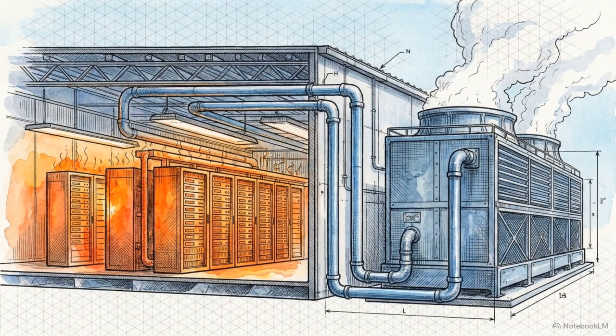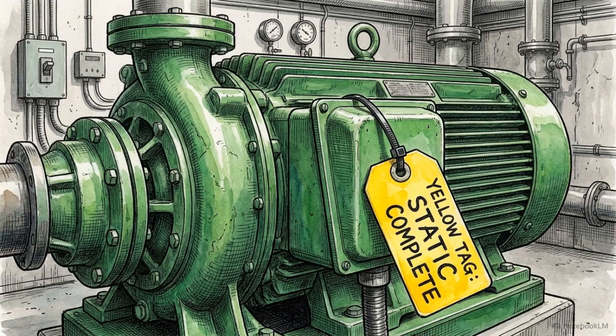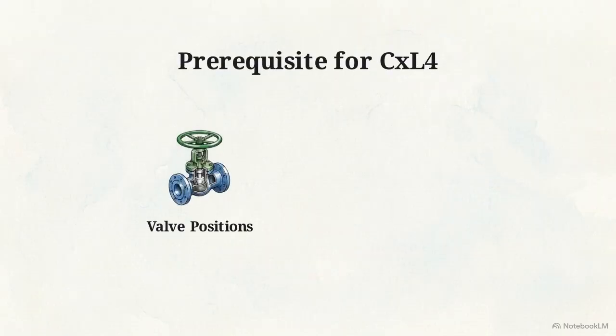Mechanical commissioning evaluates cooling as a continuous heat rejection chain, moving from the heat source to the ambient environment. The SPLC state point map charts thermal energy flow from S1, the IT heat source, through the CRAH and chilled water loops until it reaches S6 for ambient heat rejection. This chain creates absolute hold points. No pumps can be started until the pressure tests, pipe flushing, and water treatment evidence are formally accepted. Functional performance testing at CxL4 is prohibited until design flows and valve positions are recorded.